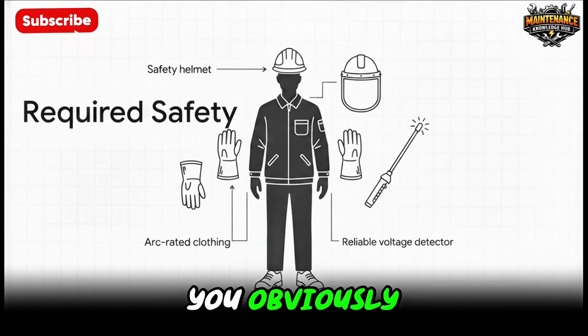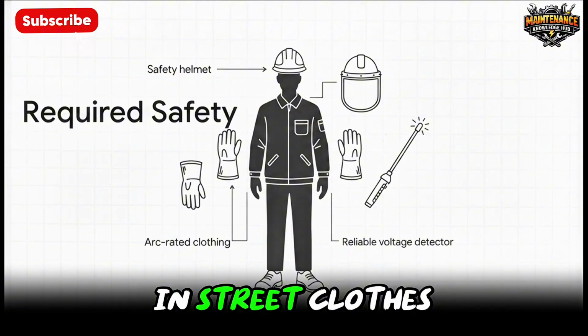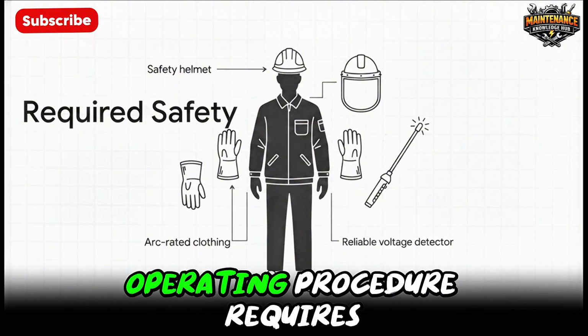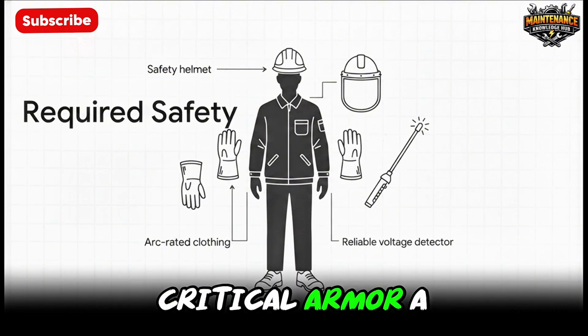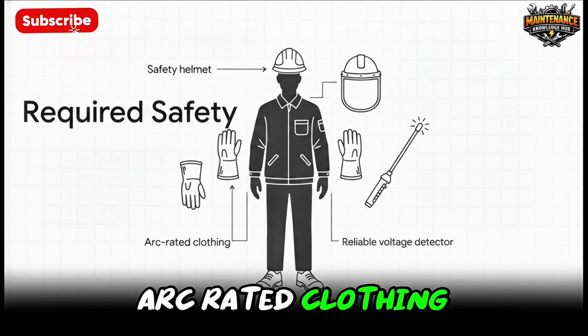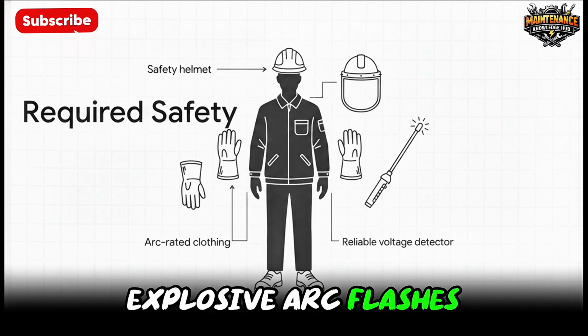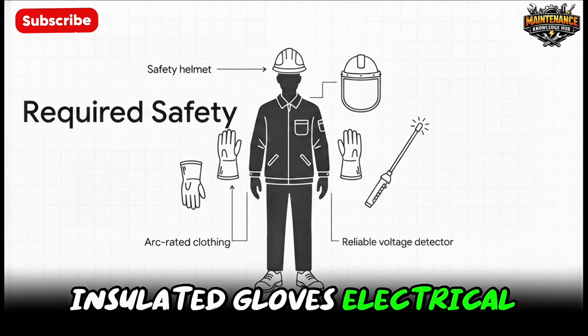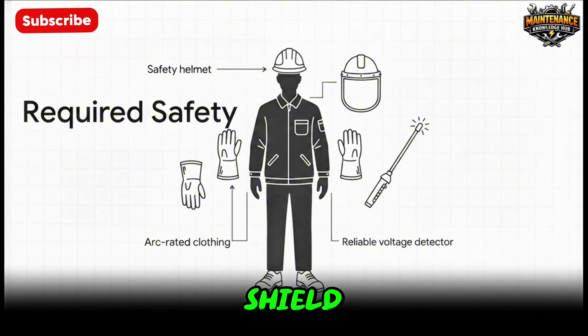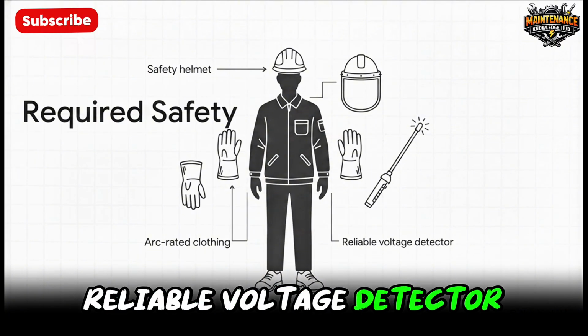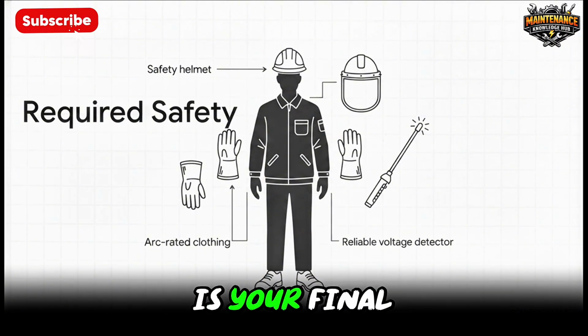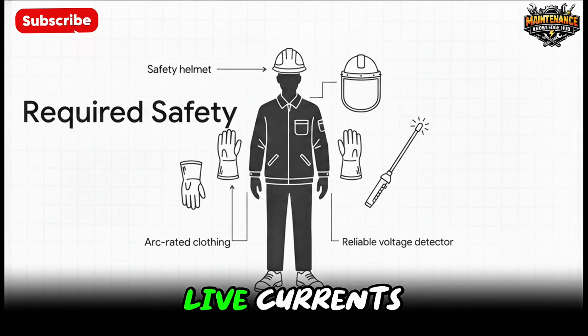I mean, you obviously can't just stroll into a switchyard in street clothes, right? The standard operating procedure requires critical armor: a safety helmet, arc-rated clothing to protect against explosive arc flashes, insulated gloves, electrical safety shoes, a full face shield, and a super reliable voltage detector. This gear really is your final line of defense against arcs and live currents.